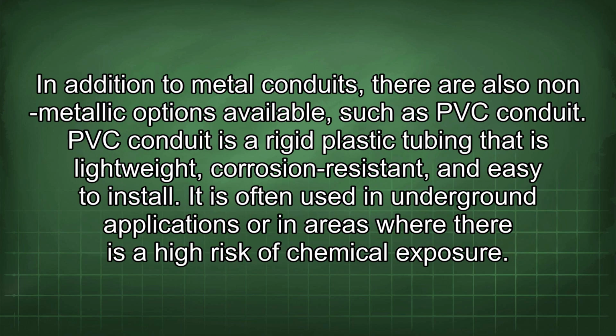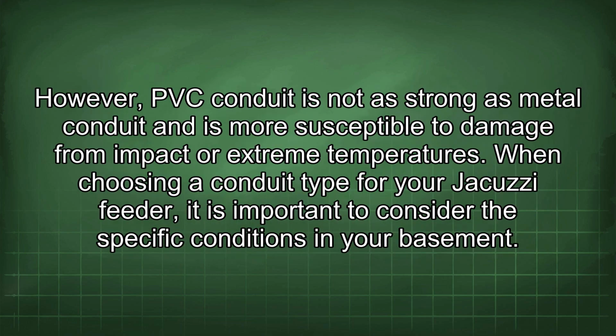In addition to metal conduits, there are also non-metallic options available, such as PVC conduit. PVC conduit is a rigid plastic tubing that is lightweight, corrosion-resistant, and easy to install. It is often used in underground applications or in areas where there is a high risk of chemical exposure. However, PVC conduit is not as strong as metal conduit and is more susceptible to damage from impact or extreme temperatures.